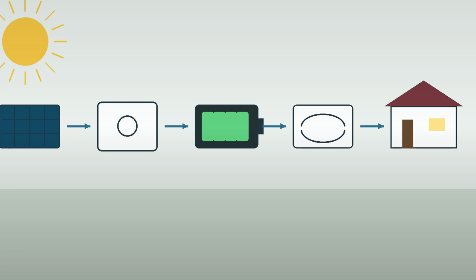Keep a system notebook. Record panel wattage, controller model, battery chemistry, battery capacity, inverter size, fuse sizes, wire sizes, commissioning voltages, and changes. Put a printed shutoff sequence near the system. If someone else has to help in an emergency, labels and notes turn a homemade system into a readable system.